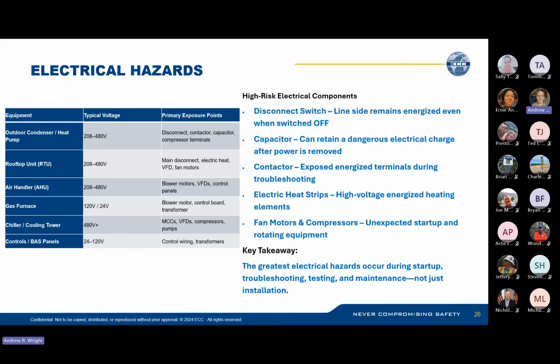Electric heat strips are high-voltage energized heating elements in ducts that get really hot like a hairdryer, and they blow air over to create heat. Those are usually what you see in systems like emergency heating. Fan motors and compressors: unexpected startup and rotating equipment. So the takeaway is the greatest electrical hazards occur during startup, troubleshooting, testing, and maintenance, not just install. Install has the least amount of electrical hazards because you haven't energized anything yet. It's usually when you're troubleshooting or doing maintenance that these electrical hazards are the most prevalent.